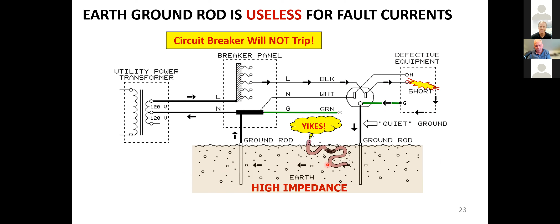It's just too dry. So anyway, that would only cause a couple of amperes to flow if there were 25 ohm connections here. And that's not going to trip the breaker. So the chassis here would stay at some very elevated and dangerous voltage. And the only other thing that would happen is the worms would all crawl out of the ground because they hate electric current flow in the soil. So if you fish a lot, there's a good way to get worms.